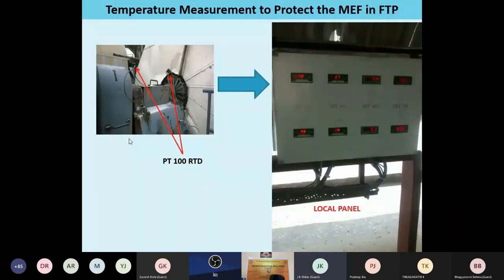Another example, I will take an RTD. Suppose for temperature measurement we have put an RTD. Suppose this is a main exhaust fan. The main exhaust fan cost is very high, some crores. So for condition monitoring, that is bearing temperature and vibration, shaft vibrations, to protect the machine we have to measure the bearing temperature. We have put RTDs, resistance temperature detectors.